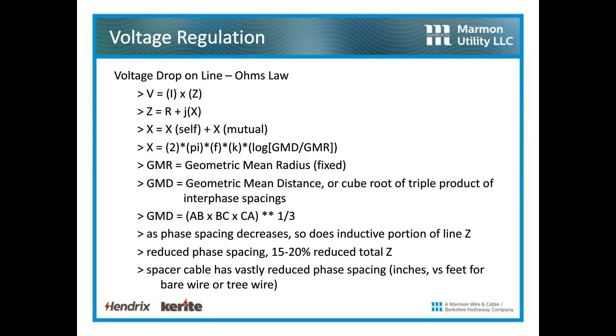Again, this material is going to be available after the webinar. People always say, I just don't understand this whole concept of better voltage regulation. Why do I get a better voltage regulation when I have the same size conductors that are using spacer cable instead of bare wire in an open construction? These are the formulas I put down here that explain it. Essentially, the formula says log of GMD over GMR for the inductive reactive part of that impedance. The geometric mean distance is the cube root of the triple product of the interphase spacings. As those phase conductors come closer together, that geometric mean distance decreases, the mutual inductance decreases, and the total impedance decreases by 15 to 20%.